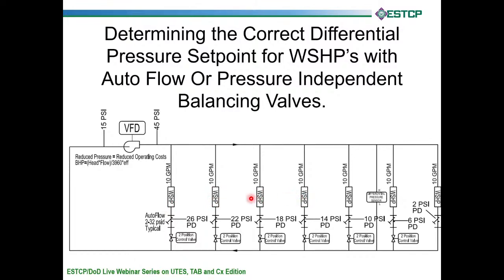A system is properly balanced when all your flow rates are proportional, and also when you have at least one fully open balancing valve in the system. So at 2 psi, this balancing valve is 100% open. So like I said earlier, you would slow the VFD down until you get 2 psi at your most remote water source heat pump, and then you would look at your differential pressure here, and that would be your set point. So your TAB contractor is the guy that's responsible for telling the control contractor what the differential pressure set point is. So your TAB contractor needs to know how to do this. Very important that we don't run that pump any faster than we have to, just waste horsepower and waste money.